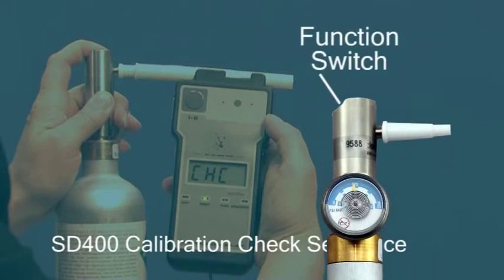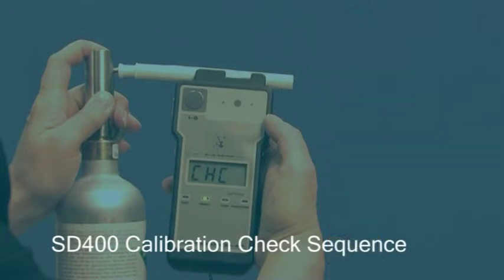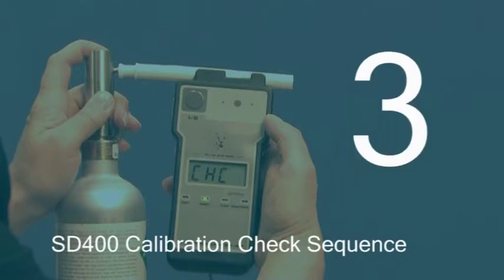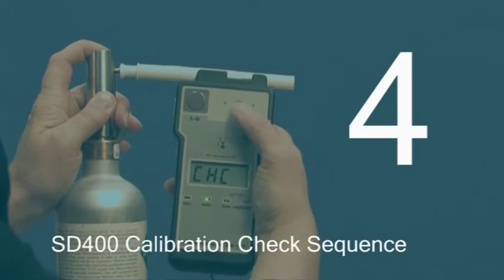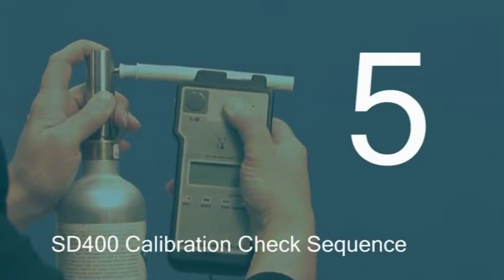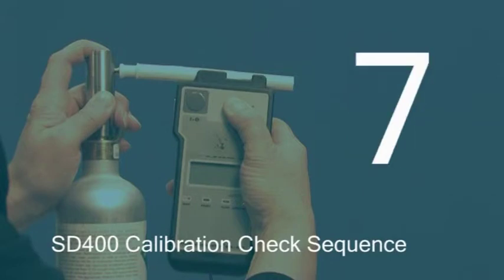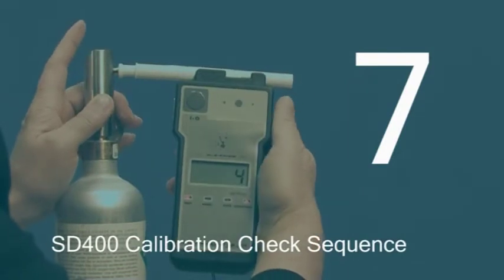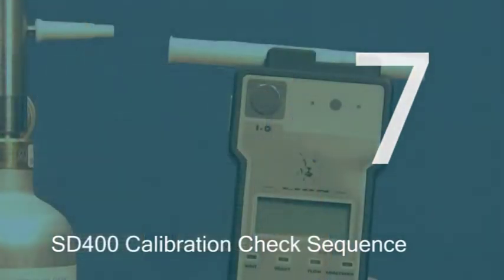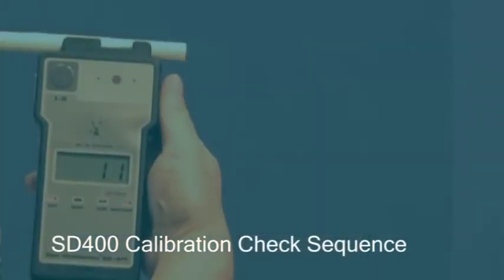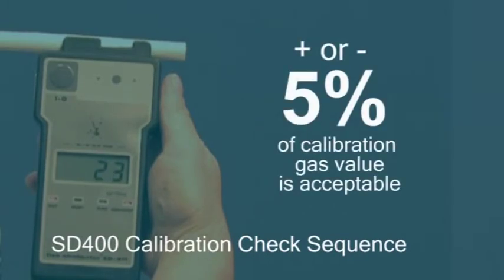Holding down the function switch on the gas cylinder, let the gas flow through the mouthpiece while you count 7 seconds, saying 1,000, 2,000, 3,000, and so on is a good estimate. As you say 5,000, press function switch C on the alcometer and keep the gas flowing through for the remaining 2 seconds. At 7,000, you can release the buttons on the cylinder and SD400 and disconnect the mouthpiece. Wait for reading. A final reading of plus or minus 5% of the calibration gas value is acceptable.